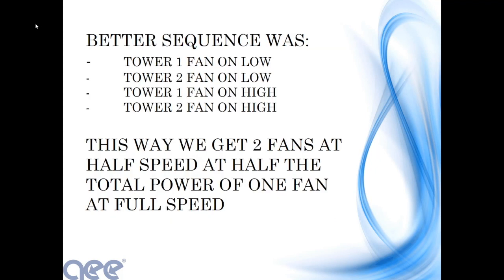So a better sequence, and this was a constant flow system, was to bring tower fan 1 on low, then go to tower 2 and bring its fan up to low speed. Now, if you're looking at a 2-winding motor, your low speed is half. Rough and dirty, a cooling tower that's pushing half its airflow through is going to provide about half its capacity. Well, now we've got 2 fans at half speed. If you know the fan affinity laws, that means we're at about 12.5% power, rough and dirty. So we're getting 1 whole cooling tower worth of heat rejection with only half the total power of 1 motor.